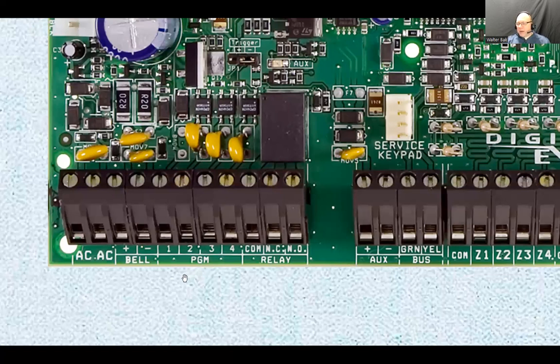All right, program 1, 2, 3, and 4. This one has 4 program terminals. Now, I'm not going to get into too much detail because different systems will have different ways of handling the program outputs. In some cases they could be programmed so that between the common terminal and that output, you could have a voltage, or you could have a dry contact relay. You will have to look at the system's manual or contact support or attend one of the training sessions that the company sells, and they do have training sessions.